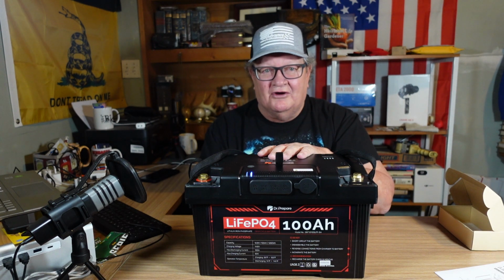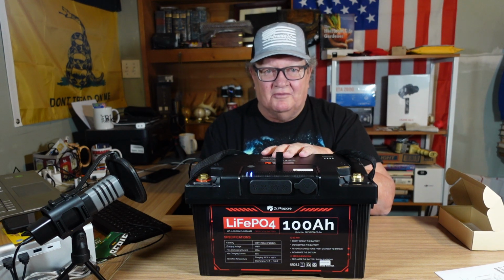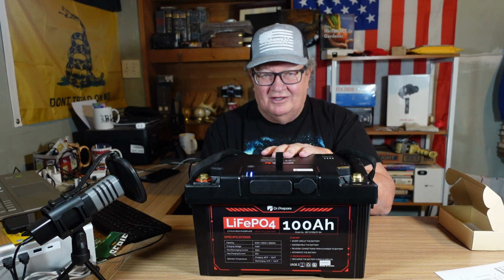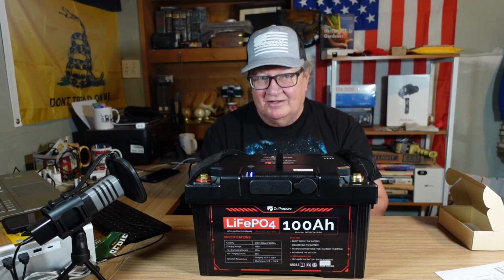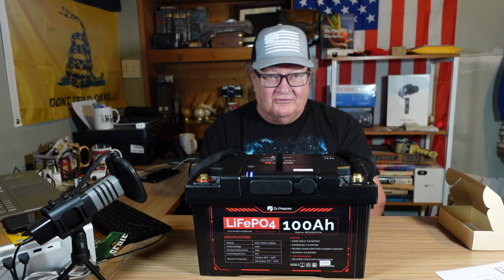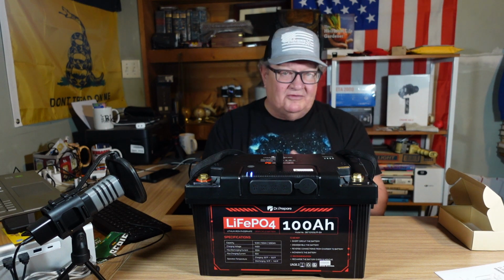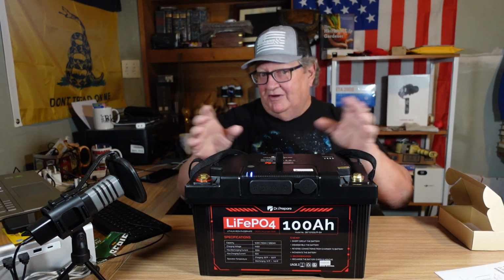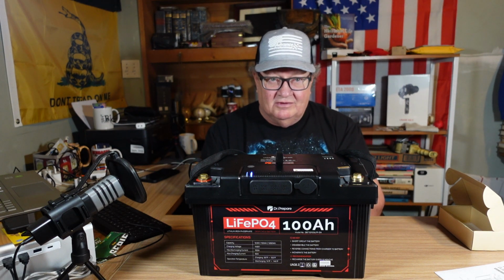3,000 duty. You can discharge it 3,000 times and recharge it before there's any noticeable change in it. So you put it in, you don't worry about it for 10 years. That's the way I look at it. And if you take care of them, it's probably 20 years or so you can go with them. And totally 100% maintenance free. Once you put them in there, don't look at them again. You don't need to. They're just there.